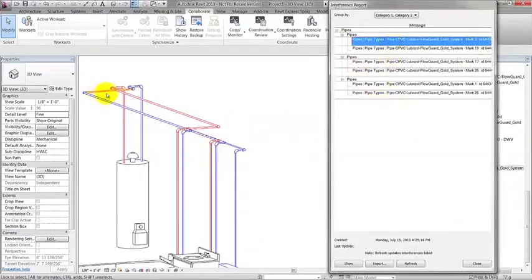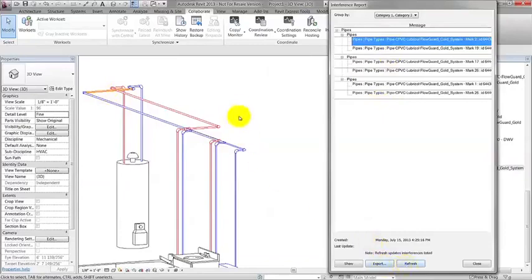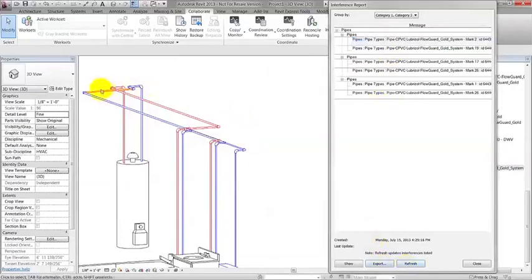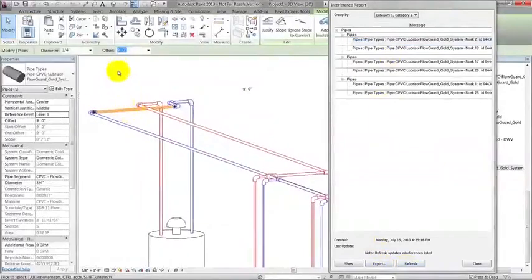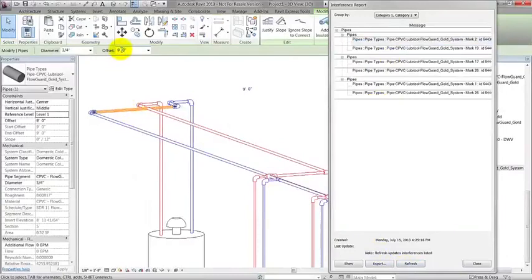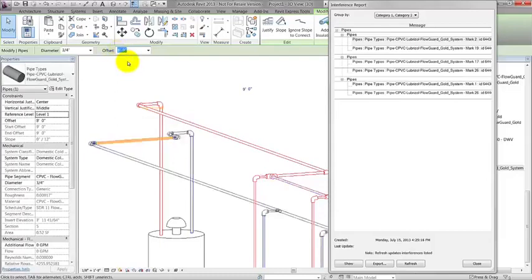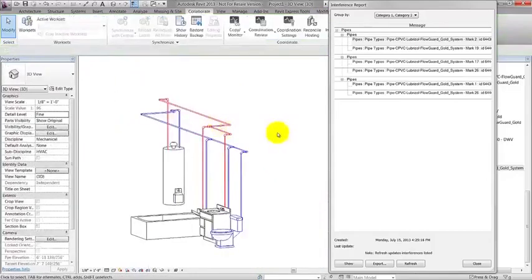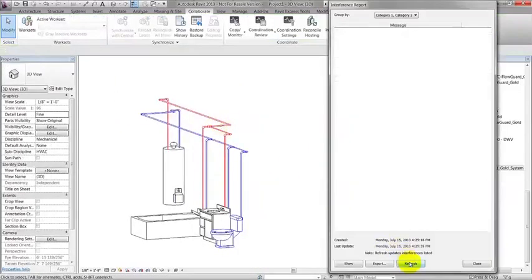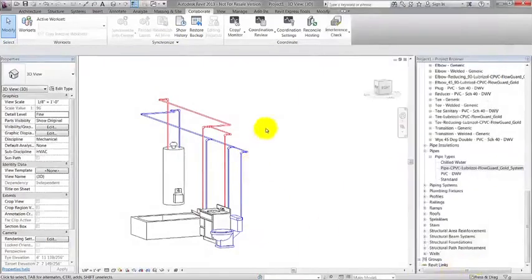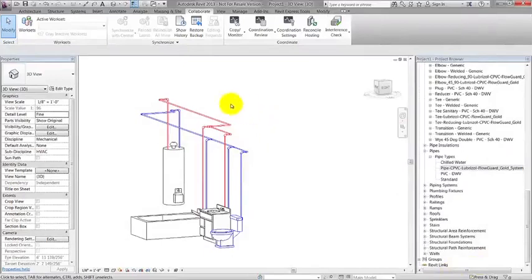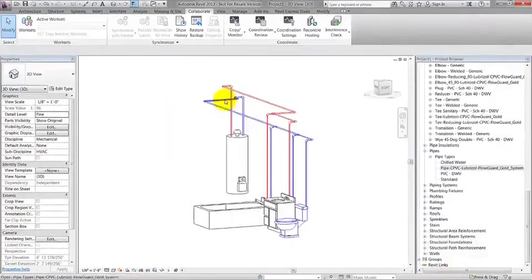A list of pipes appears. Click on any of the pipes in the dialog and see how the actual pipe highlights in the model. I see that the pipes are at the same height. I can fix them by changing the dimension in the offset on the ribbon. I'll change it to 8 feet in this case. Then I'm going to click Refresh in the Interference Report and see that no interferences came up this time. All the system's pipes that were at the original height of 9 feet were automatically changed to 8 feet, fixing all other interferences.